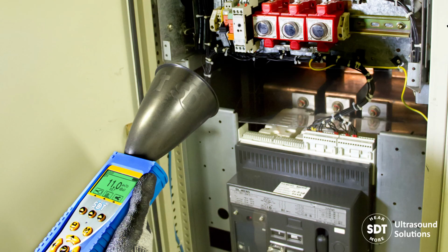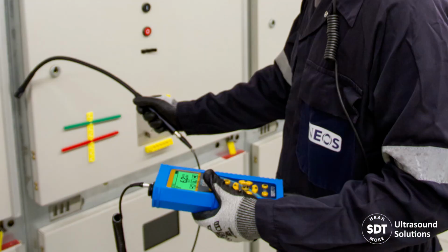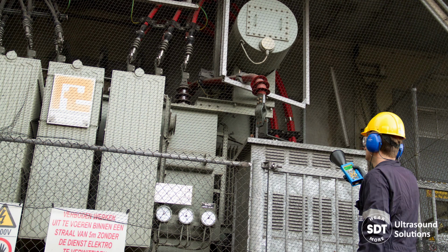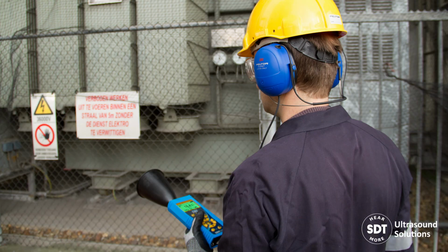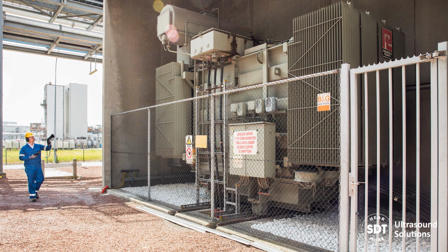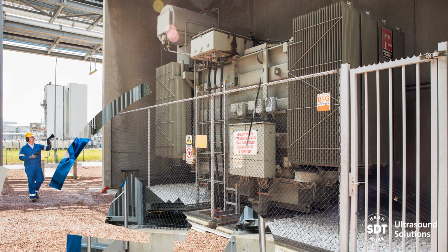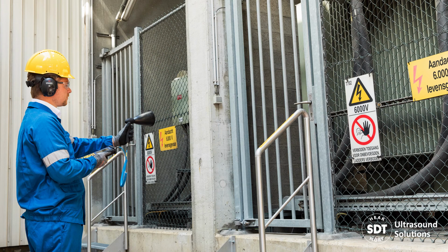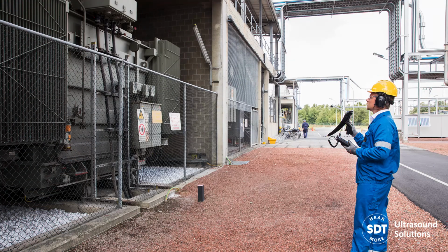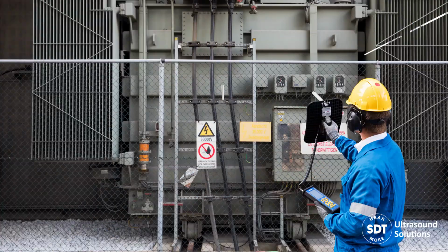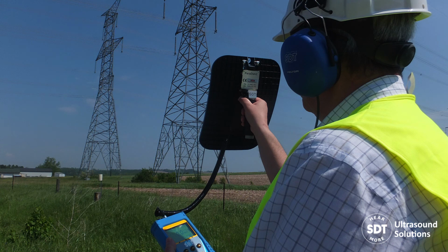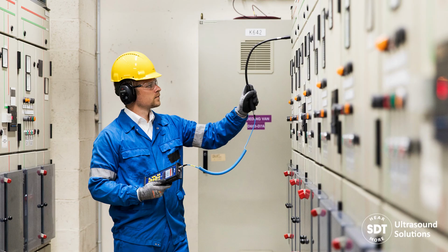Ultrasound presents a triple win solution. It reduces the risk of arc flash exposure, ensures equipment reliability, and allows inspectors to work at a safe distance from high voltage assets. Notice in all these photos that the inspector is on the safe side of the fence. Ultrasound detects defects which, when left to deteriorate, could lead to an arc flash event. This doesn't suggest that ultrasound removes the need for personal protective equipment and other safety measures. I'm yet to meet an arc flash suit which can detect an arc flash at its inception. But if an arc flash suit is the last line of defense, then ultrasound should be your first.